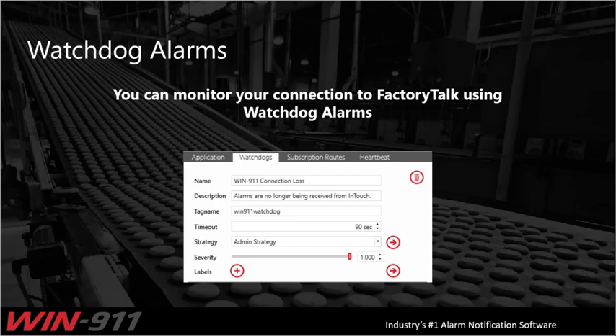For the watchdog part of WIN911 talking to InTouch, you can monitor that connection by monitoring a tag for a changing alarm state, which means you need to create an alarm in InTouch that changes state automatically. WIN911 would be monitoring for that value change, and when it doesn't change within a specified timeout — for example, 90 seconds — it would send out the watchdog alarm. You'd also want to filter your alarm summary to exclude this alarm so it doesn't clutter your summary, or send it to a custom strategy set up just for the watchdog or heartbeat.